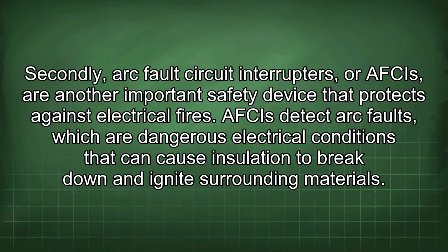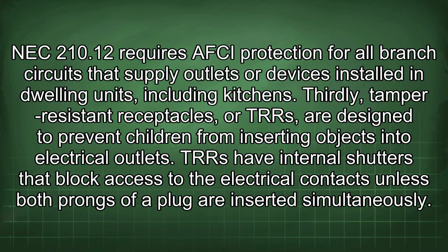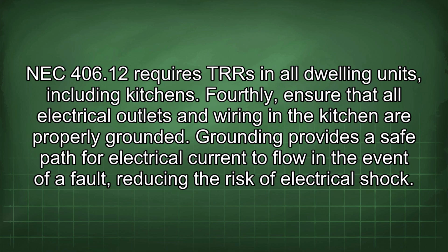Secondly, arc fault circuit interrupters, or AFCIs, are another important safety device that protects against electrical fires. AFCIs detect arc faults, which are dangerous electrical conditions that can cause insulation to break down and ignite surrounding materials. NEC 210.12 requires AFCI protection for all branch circuits that supply outlets or devices installed in dwelling units, including kitchens. Thirdly, tamper-resistant receptacles, or TRRs, are designed to prevent children from inserting objects into electrical outlets. TRRs have internal shutters that block access to the electrical contacts unless both prongs of a plug are inserted simultaneously. NEC 406.12 requires TRRs in all dwelling units, including kitchens.